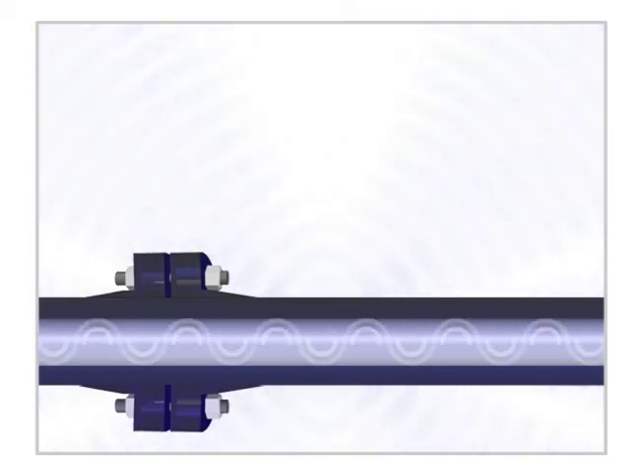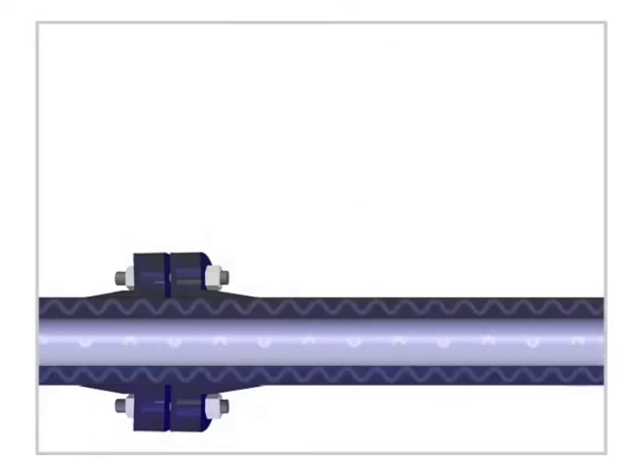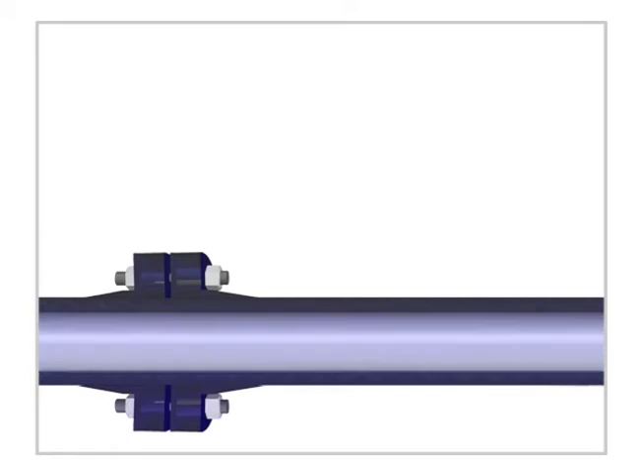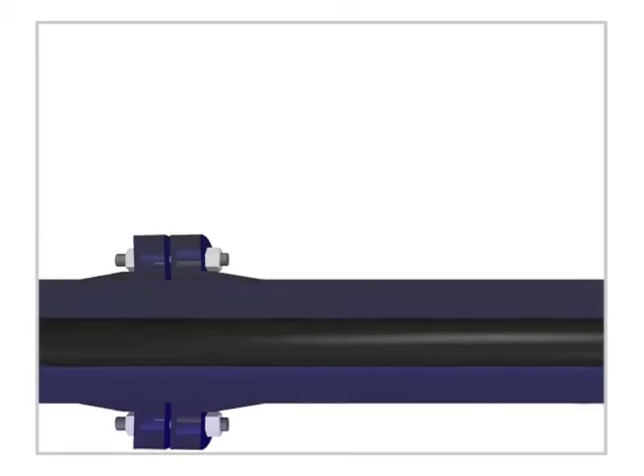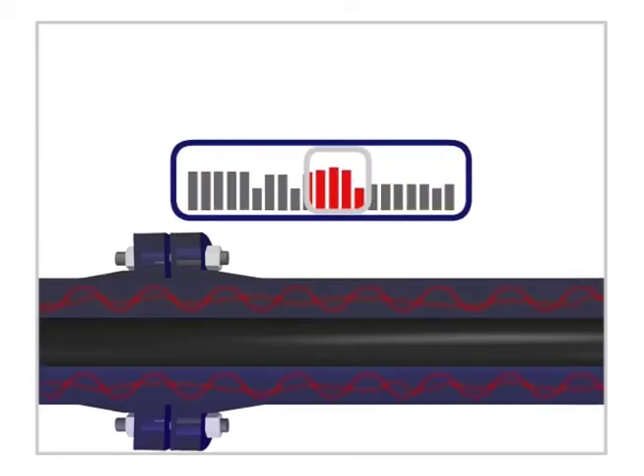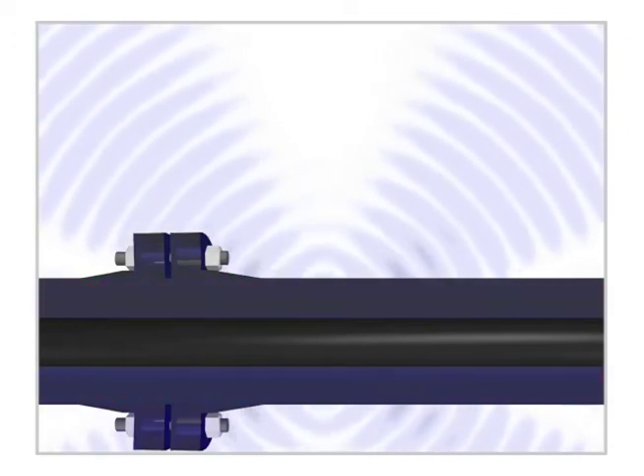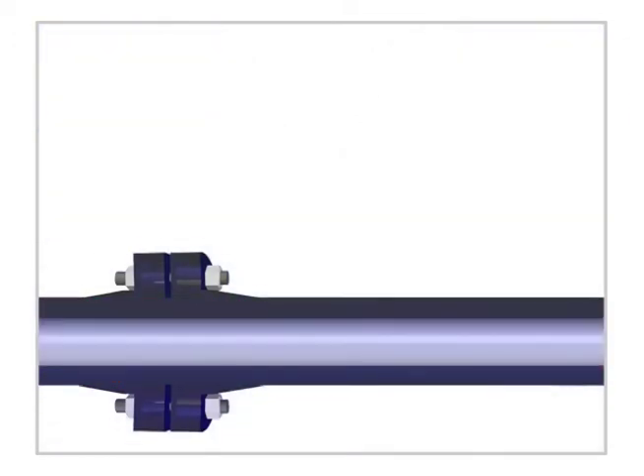The fluctuating internal wall pressure field excites a vibration in the pipe wall. Depending on the pipe diameter, material, and pipe wall thickness, some noise frequencies will radiate through the pipe wall and create sound waves that people can hear.